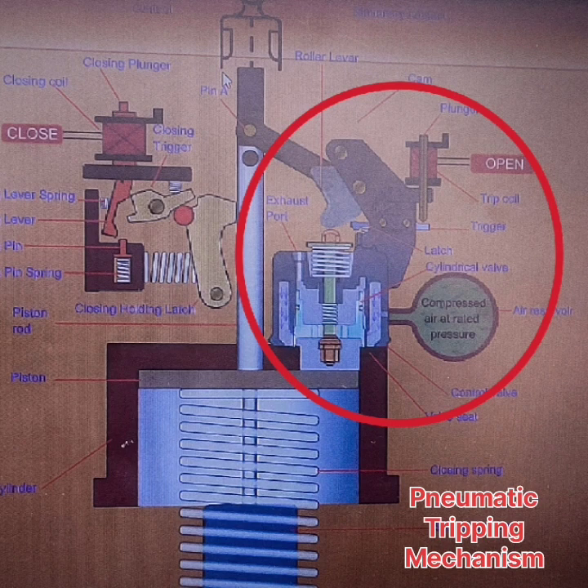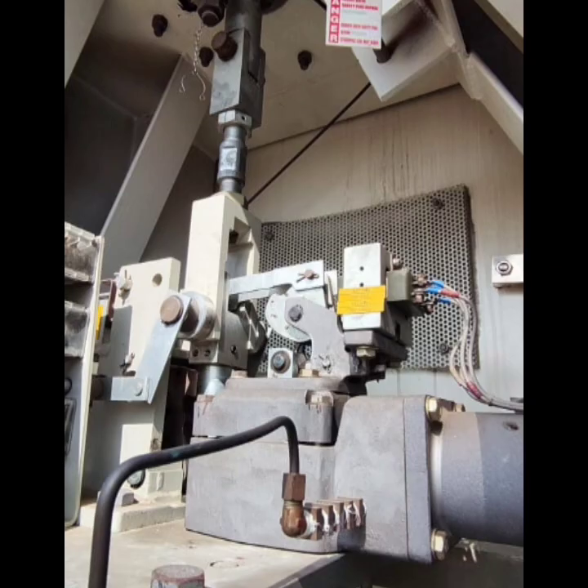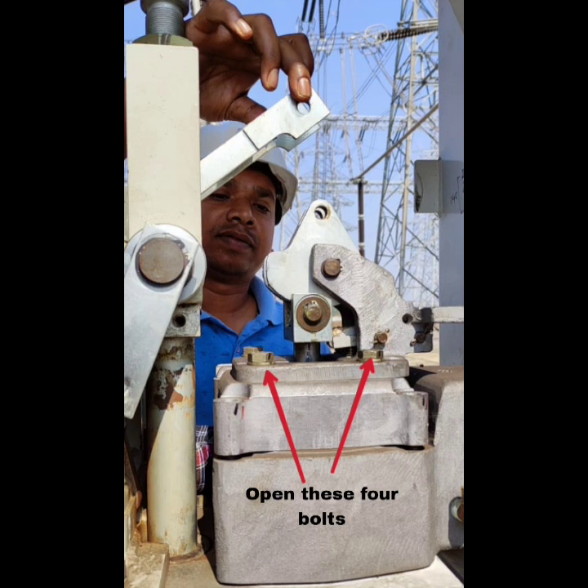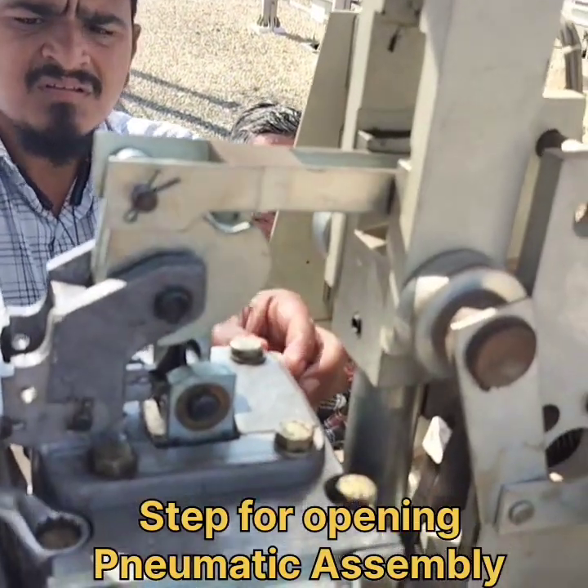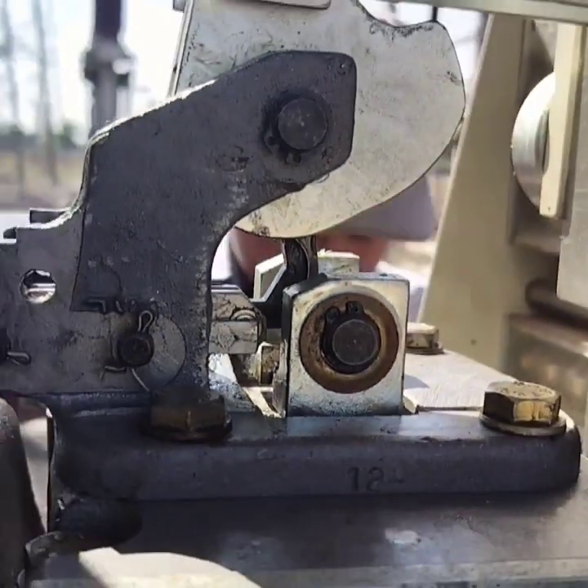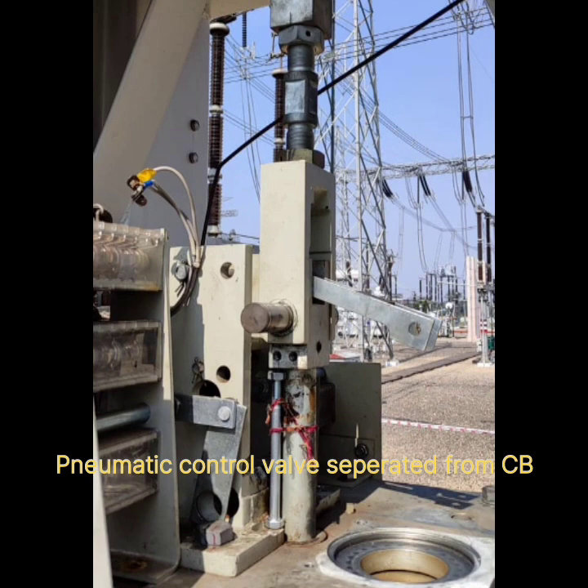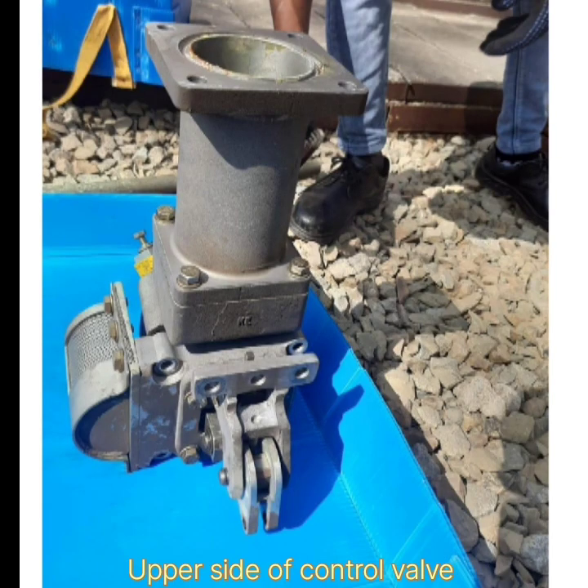Overhauling of pneumatic tripping mechanism. This is the pneumatic housing; it consists of the tripping coil, control valve assembly, and pneumatic housing. For the removal of control valve assembly, we open these bolts. After this process, we detach the trip coil and remove the control valve assembly. These are images of the pneumatic control valve assembly after separation from the circuit breaker.